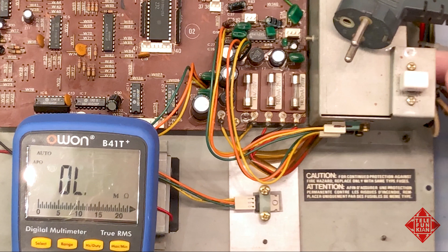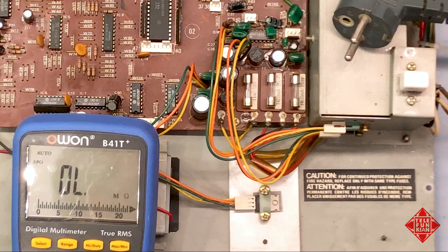So how can that be? Well, I've already checked the primary fuse, located beneath this panel, and it's good. So what else is there? All there is between this end of the cable and the transformer is this switch. So either the transformer winding is open, or we have a dud switch.